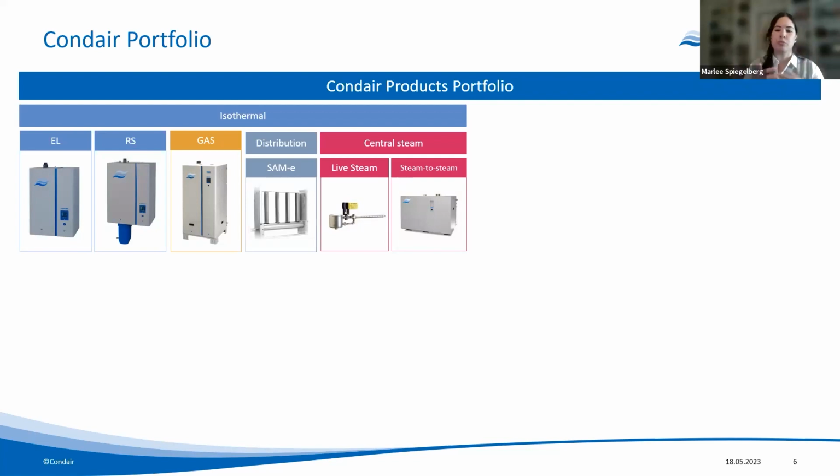That, again, uses boiler plant steam. You can either inject it directly into the duct with the live steam system, or you can do a steam-to-steam exchange with fresh water with that SE at the far right-hand side. Then you can direct the steam either to a distributor in the space, like a blower pack, or you can distribute it within a duct or air handling system, which is the most common application we see. Our common distribution is called the SAM-e.